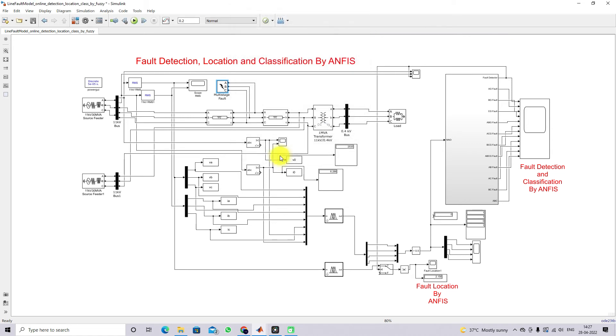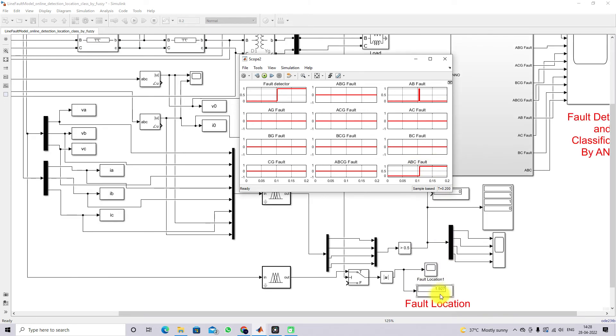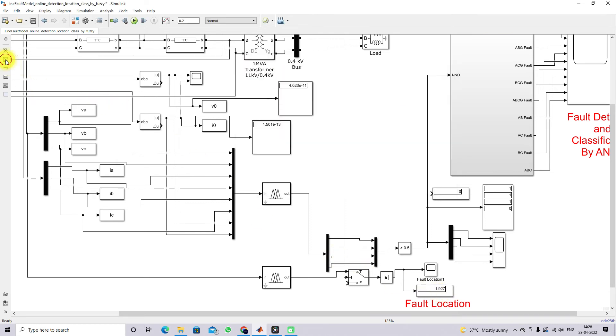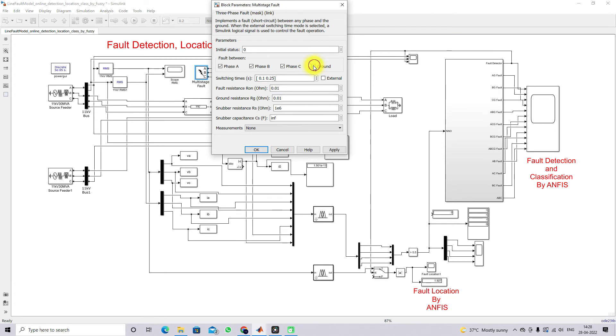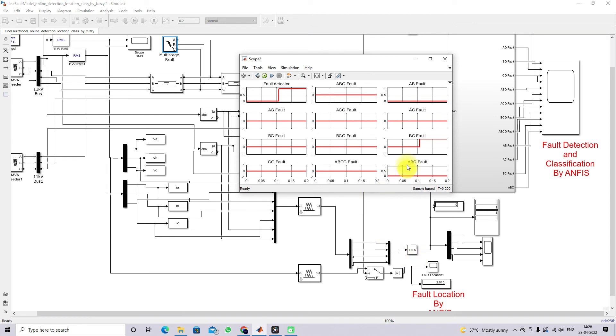Checking results for AB ground fault: the fault is detected and fully classified as AB ground fault. The fault location is around 2.1 to 2.2 kilometers. Changing the fault to ABC fault — a triple-line fault. After simulation, the fault is detected and classified as the ABC fault. The fault location is around 1.9 kilometers, while we fixed it at 2 kilometers. Next, changing to double-line fault (BC fault): the fault between lines B and C is detected and classified as a BC fault, with location around 2.015 kilometers.